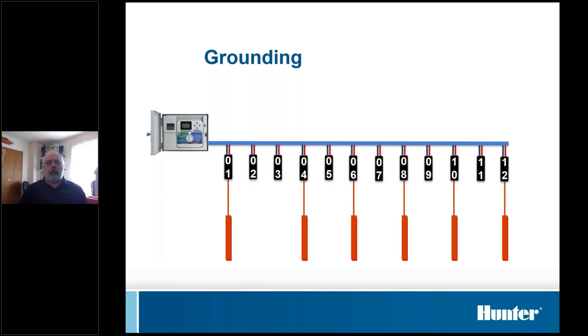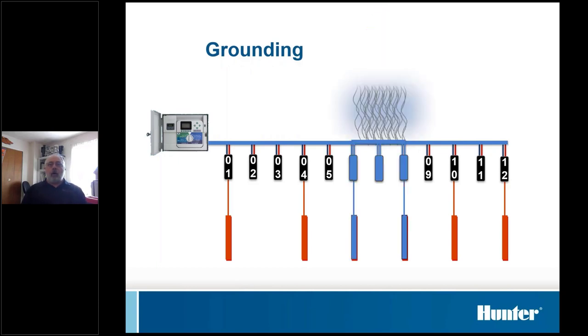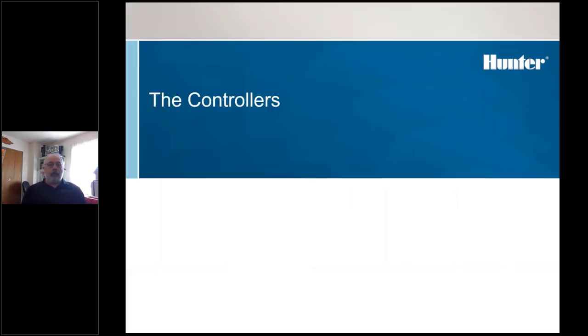So here's how grounding works, or at least what we're attempting to do here. When you take a lightning strike, we're trying to hold that surge between the two grounding devices. Anything in between is vulnerable to damage. But what we're trying to do is not let it get out into the rest of the system. You certainly don't want it to get back to the controller and then out the other wire paths, and it could get real bad. But that's the idea. We can't stop lightning. Lightning will do what lightning decides it's going to do. We're just trying to minimize damage.